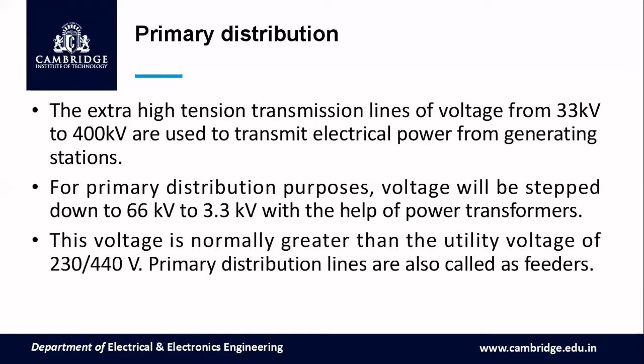Now that will be stepped down. Whatever the 66 or 33 kilovolt is, will be stepped down to 3.3 kilovolt. When the utility receives it, they should receive a voltage of 230 or 440 volt. The primary distribution lines are transmitted with the help of these feeders. These distribution systems are capable of handling large blocks of power. For a load requirement of 5 MVA or less, the secondary distribution system transfers power out of 33 or 11 kV secondary substations with 3 to 4 feeders.